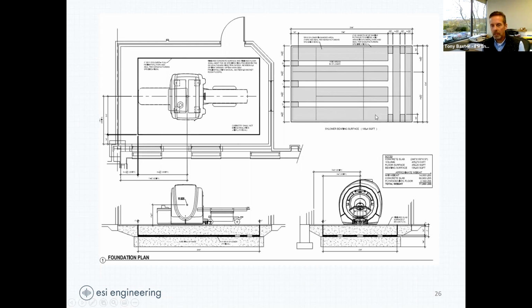But we ended up, to get the loading right and to get the natural frequency of this slab low enough, we had to use it in strips, in this plan view kind of arrangement. But it worked. We were able to get those amplitudes down below that criterion curve, at least low enough that the MRI operates and they don't have problems.